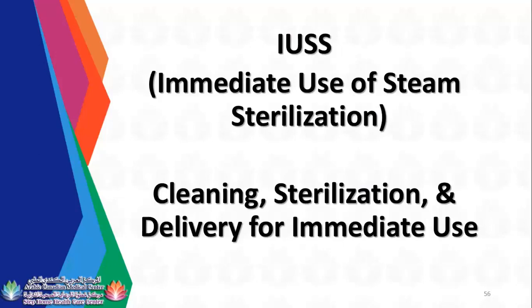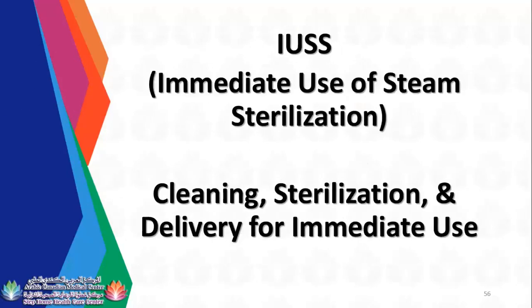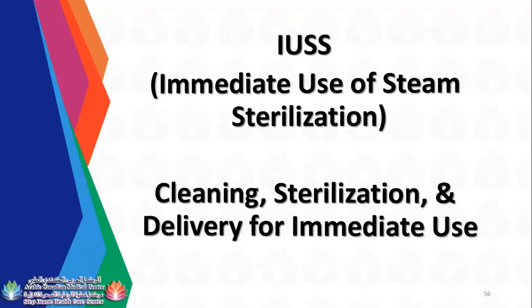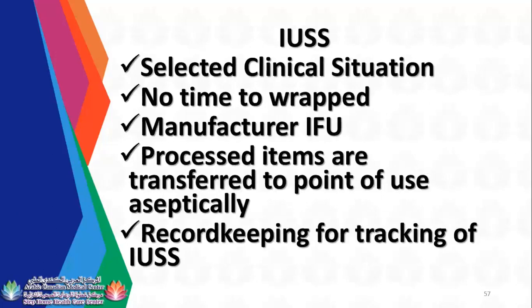So cleaning, sterilization, and delivery for immediate use is one of the main protocols to be followed, which means it should be cleaned, manually brushed, mechanically brushed, and dried. Pouching is not needed, it's okay, because that's the purpose of IUSS. You don't need to pouch the instruments. For delivery for immediate use, you need to check how you can deliver it aseptically without contaminating the instruments. Selected clinical situation, no time to wrap: you don't have time to put pouches or wrap the tray, or to clean a rigid container, because it's an emergency procedure that needs instruments right away.